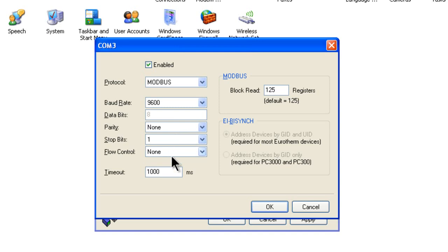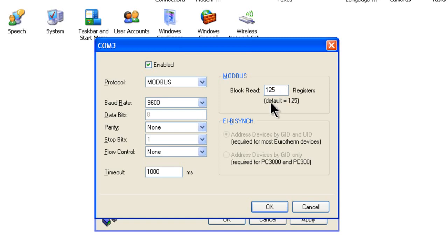Protocol is Modbus. Baud Rate is 9600. Data Bits is 8. Parity is None. Stop Bits is 1. Flow Control is None. Time Out is 1000 milliseconds. And Block Read is 125 registers. Next, click on the OK button.